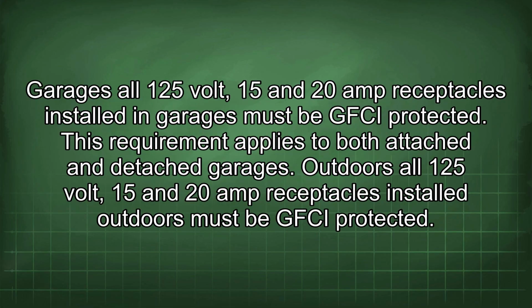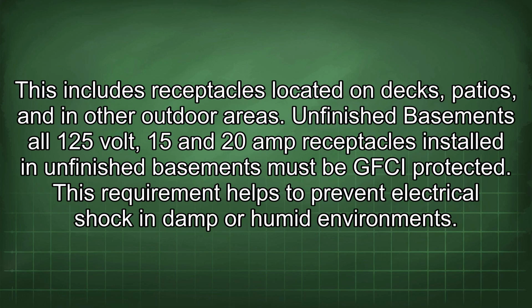Garages, all 125 volt, 15 and 20 amp receptacles installed in garages must be GFCI protected. This requirement applies to both attached and detached garages. Outdoors, all 125 volt, 15 and 20 amp receptacles installed outdoors must be GFCI protected. This includes receptacles located on decks, patios, and in other outdoor areas.